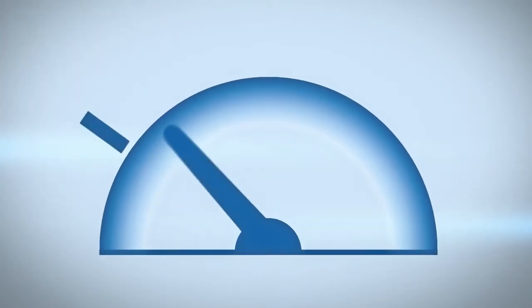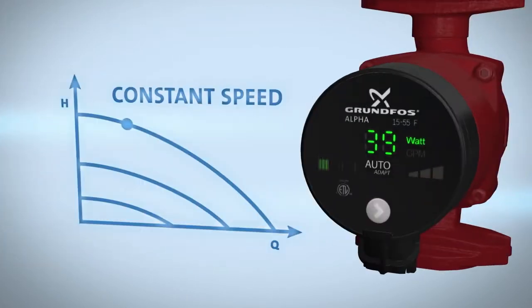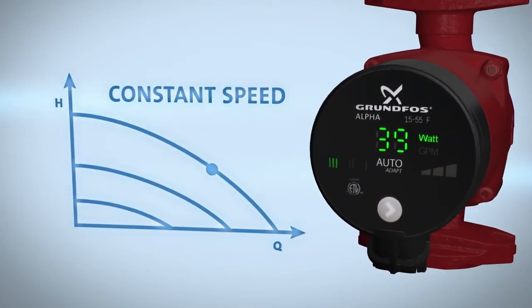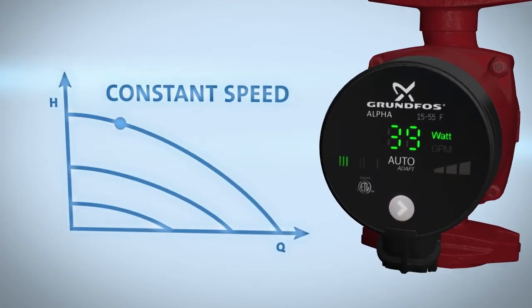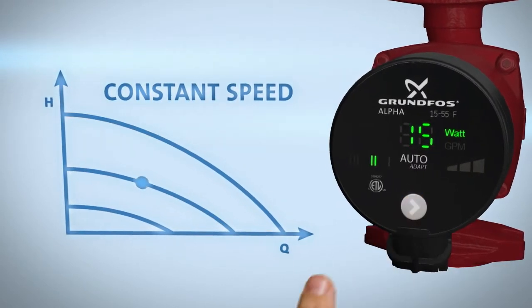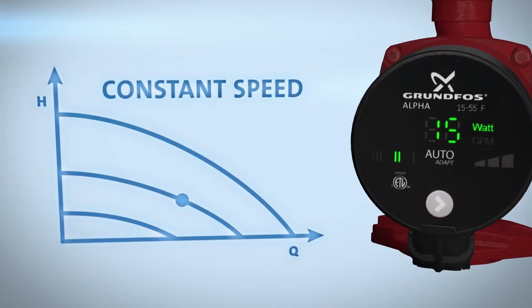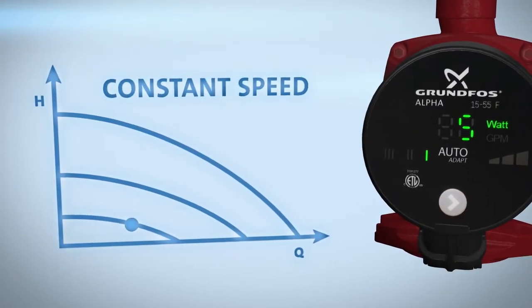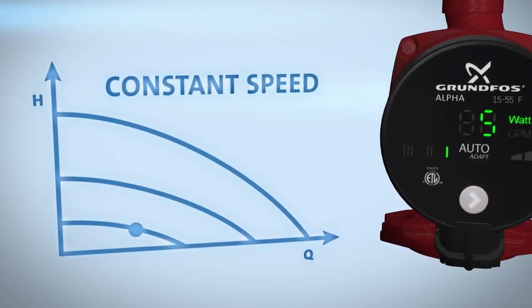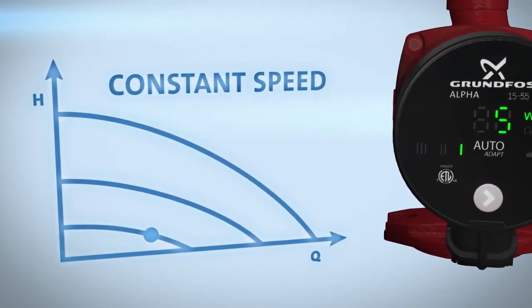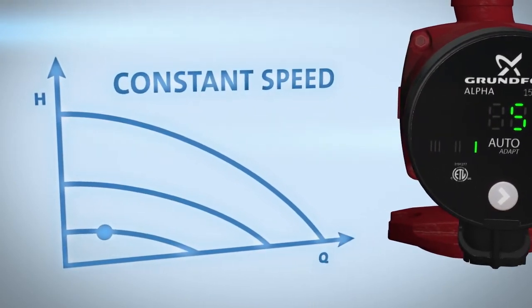Three speed modes offer even greater control. Use Speed 3 for large heating systems with constant loads and to vent the pump. Speed 2 works best for medium-sized systems with constant loads. Speed 1, the minimum speed setting, is ideal for small heating systems with constant loads and when adjusting bypass valves.